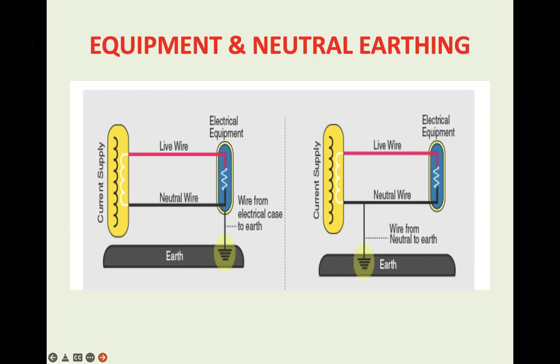To take care of that, we have two important factors: equipment and neutral grounding and earthing. To stabilize your voltage, to avoid the floating voltage, you have to provide neutral earthing. And to take care of your assets as well as the person working in that area, you have to provide equipment earthing.